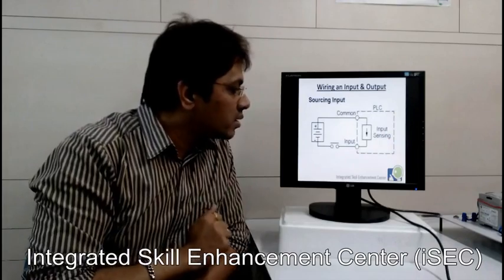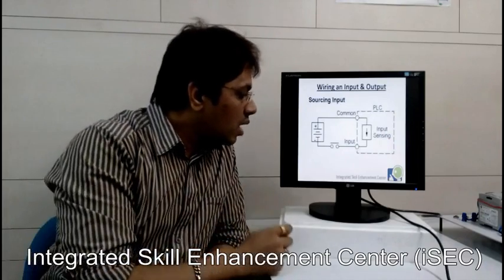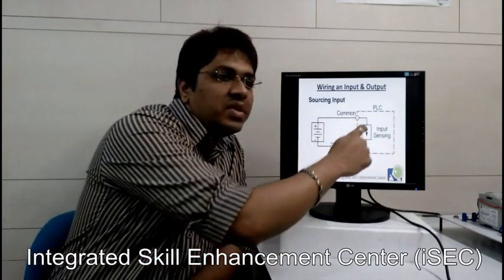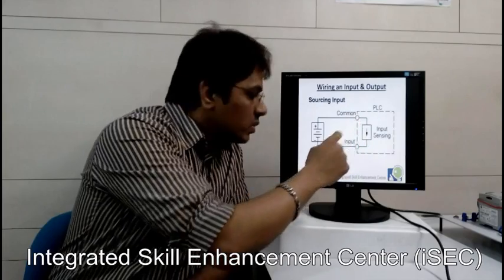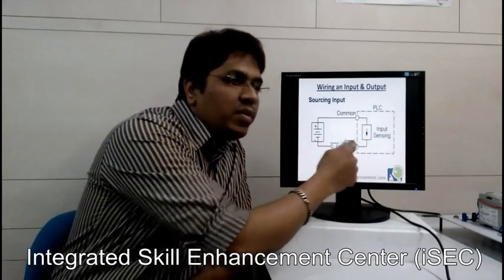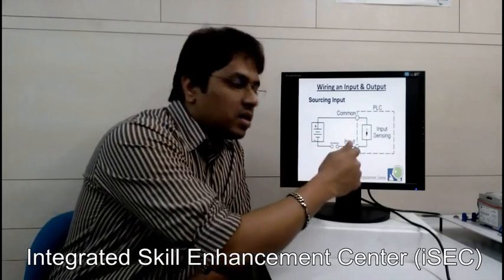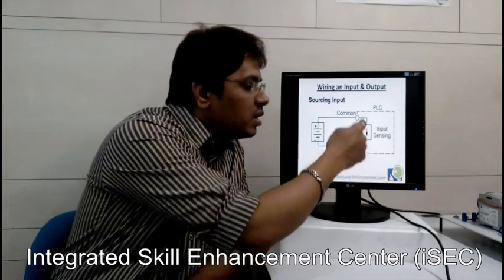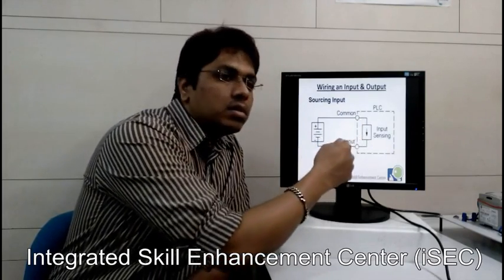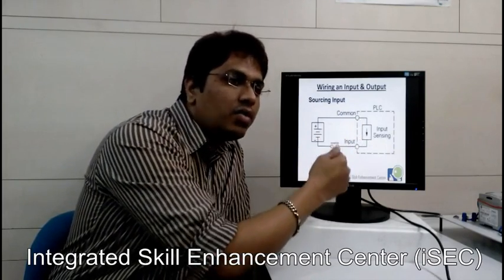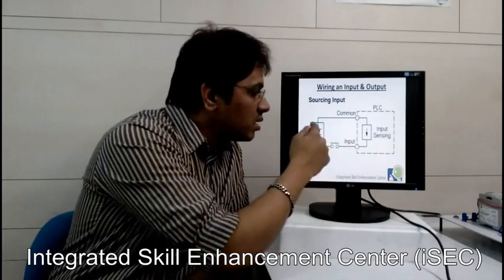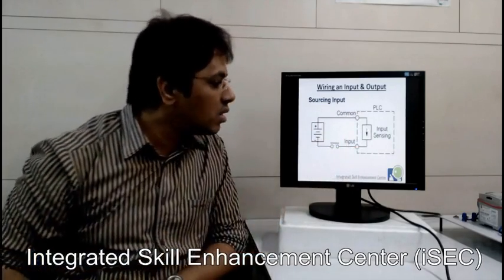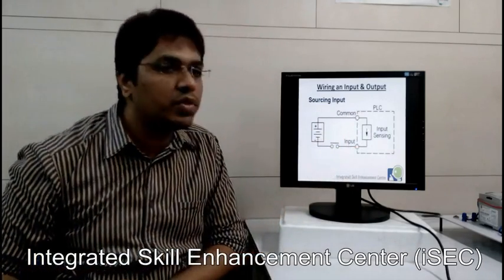Now what is sourcing input? In sourcing input, the common will be VCC, and the negative will be provided from external. Whenever you press the button, a ground is provided from the external and the path completes. So this is called a sourcing input manner.